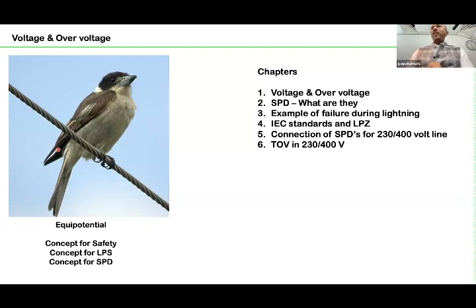SPM consists of protecting the electronics from conducted and radiated effects of lightning. Radiated effects can come through air. They can pass through air and destroy electronics. They can create surges in the wiring system, and those surges can kill the electronics. So for protecting the entire electrical and electronic system, you need SPM. SPD is only a device which is going to create equipotential bonding during a transient condition. This difference you should always understand, because sometimes people expect SPD to protect the entire electronics, but sometimes it doesn't.